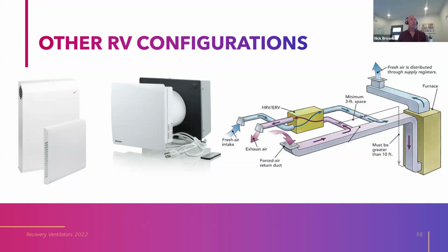The other option is ducting your recovery ventilator into your main HVAC distribution system. Here's why I don't recommend that. We're generally moving 50, 100, 150 CFM with our recovery ventilator, right? Any more than that, we're probably exceeding the amount we need for health, and we're using more energy than we need. But the duct systems for our HVAC systems, 3, 4, 5 tons, are designed for 1,500, 2,000 CFM. So if you put 100 CFM in a distribution system designed for 2,000, you really have no control over where that air is going. You get me? So that's why I really recommend a dedicated distribution system.